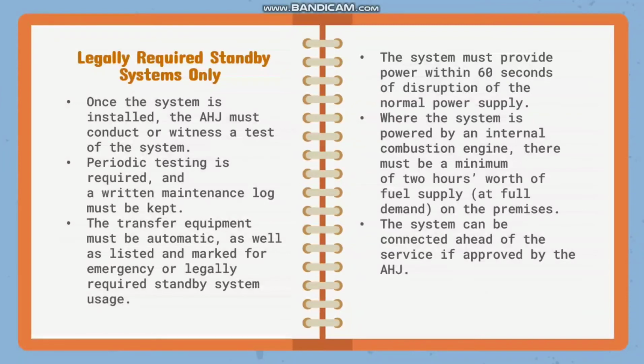The system must provide power within 60 seconds of disruption of the normal power supply. Where the system is powered by an internal combustion engine, there must be a minimum of 2 hours' worth of fuel supply at full demand on the premises. And last, the systems can be connected ahead of the service if approved by the AHJ.